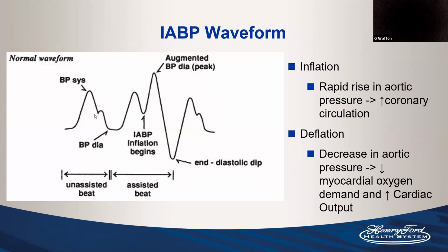So this is the waveform that you will see on the console of the balloon pump. What it's initially showing is an A line essentially, so you can see the systolic and diastolic blood pressures. And then the second wave, you see the systolic blood pressure, and then at the dicrotic notch is when the balloon pump will inflate. So then there's an increase; the highest blood pressure is during inflation of the balloon pump, and then it deflates quickly for a significant afterload reduction and that low blood pressure.